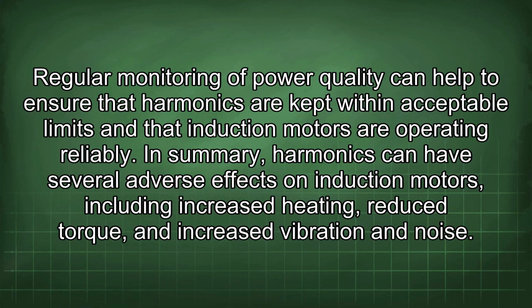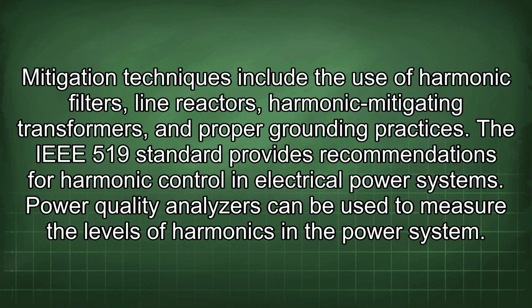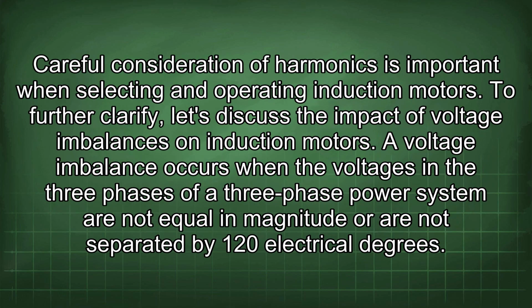motors are operating reliably. In summary, harmonics can have several adverse effects on induction motors, including increased heating, reduced torque, and increased vibration and noise. Mitigation techniques include the use of harmonic filters, line reactors, harmonic mitigating transformers, and proper grounding practices. The IEEE 519 standard provides recommendations for harmonic control in electrical power systems. Power quality analyzers can be used to measure the levels of harmonics in the power system. Careful consideration of harmonics is important when selecting and operating induction motors.